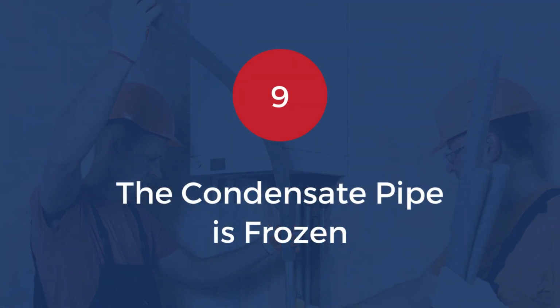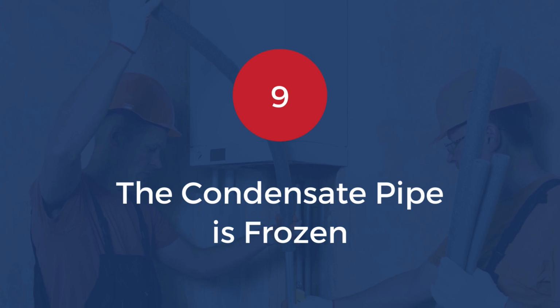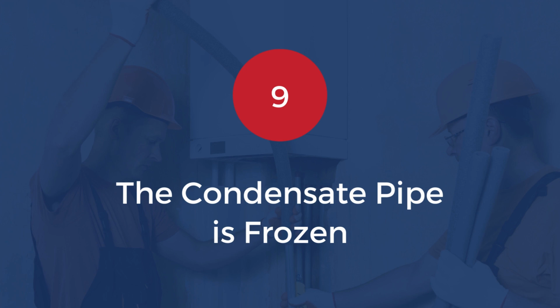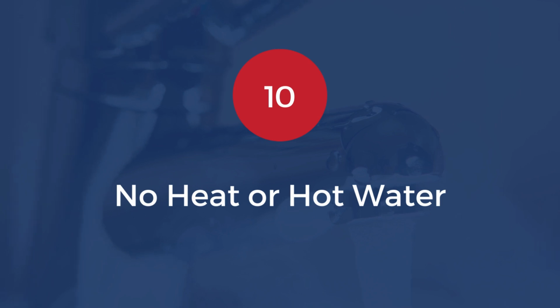9. The condensate pipe is frozen. Wastewater is carried away from a boiler by PVC pipe that empties outside. Unfortunately, the pipe is vulnerable to freezing in harsh winter conditions, and a frozen condensate pipe will prevent proper drainage and cause water buildup inside the boiler. If your boiler seems sluggish and you can see your condensate pipe isn't draining, you may need the assistance of a trained professional who can locate the frozen spot and thaw it out. You can try pouring hot water on the outside section of the pipe to see if you can unfreeze it yourself.